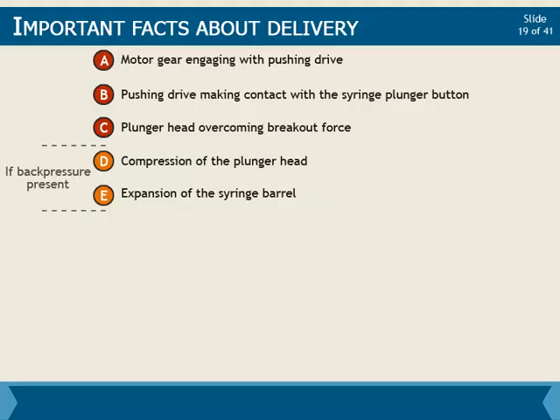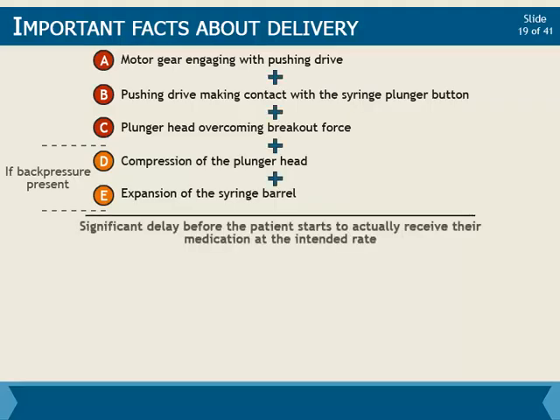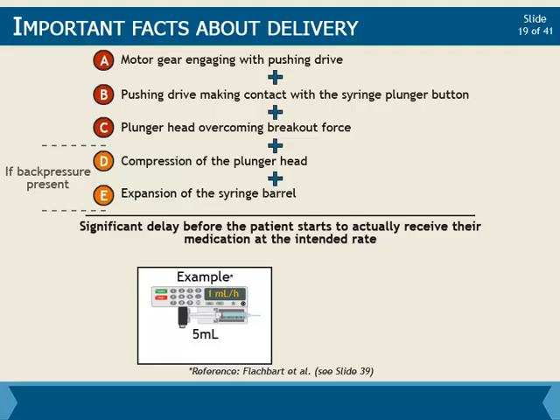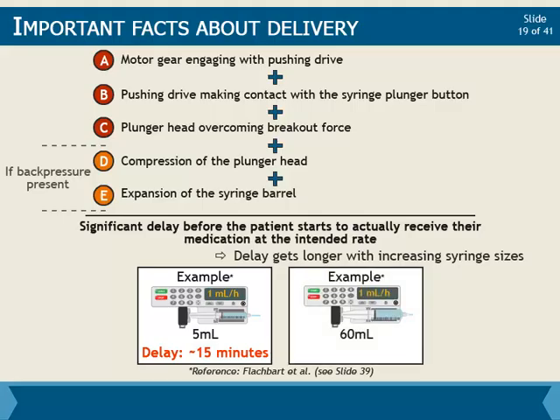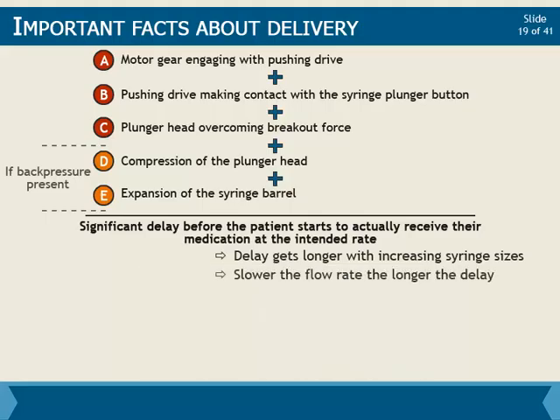While each of these events alone may seem minimal, they can add up to a significant delay before the patient starts to actually receive their medication at the intended rate. For example, when infusing at 1 milliliter per hour, a 5 milliliter syringe may take up to 15 minutes before the patient starts to receive their medication. This delay gets longer with increasing syringe sizes, and 60 milliliter syringes infusing at 1 milliliter per hour may take up to half an hour. In addition, the slower the flow rate, the longer the delay will be, because the pump is moving more slowly, meaning each of these key events will take a much longer time to finish.